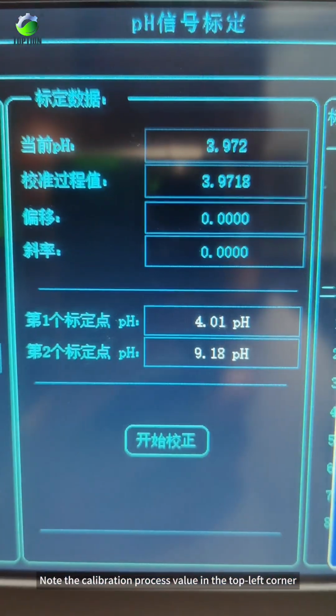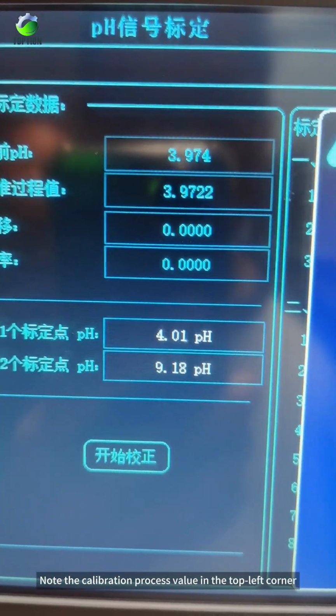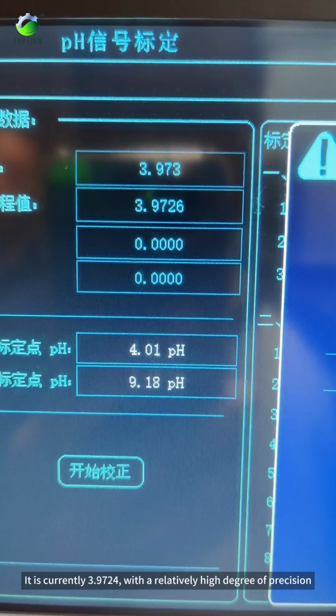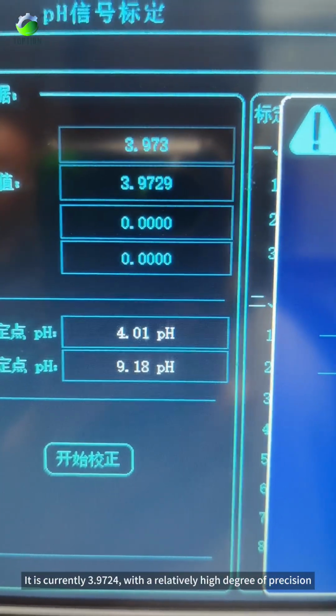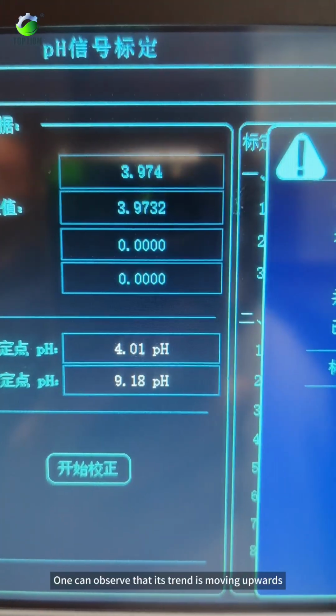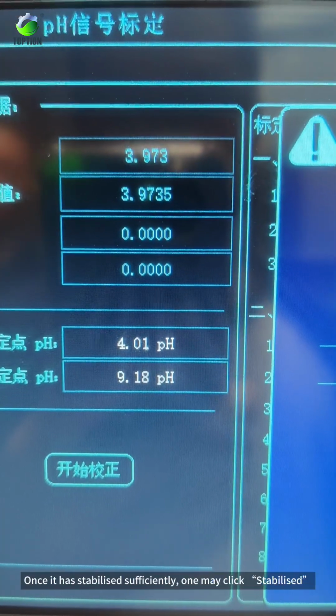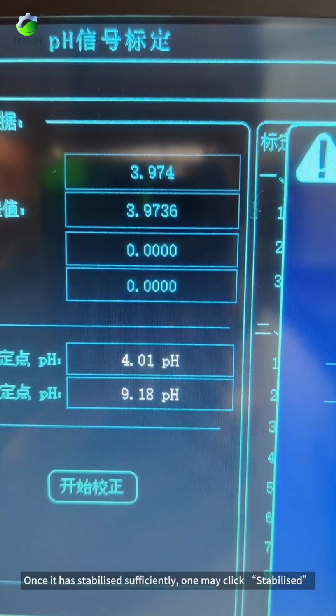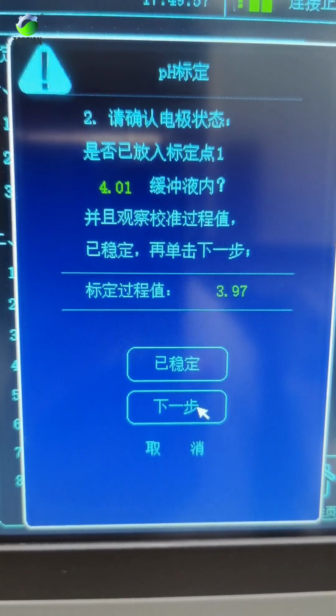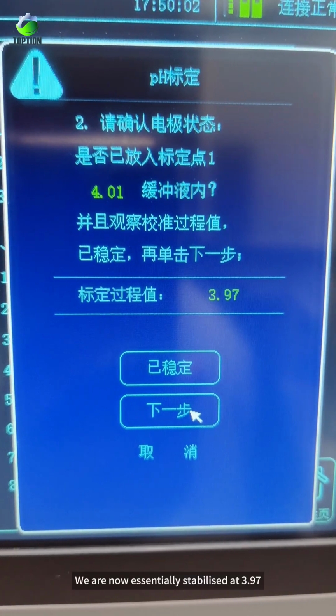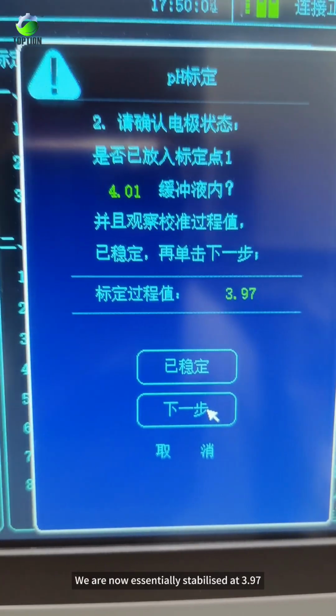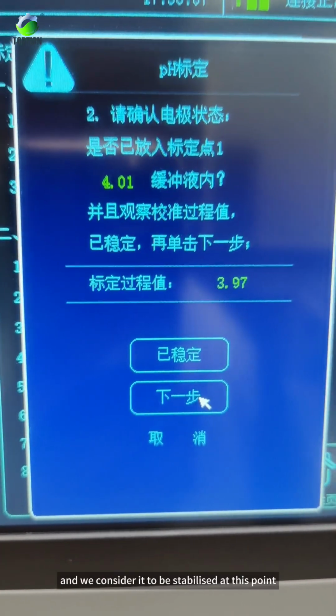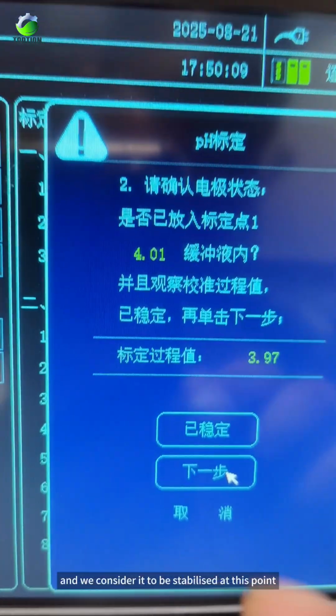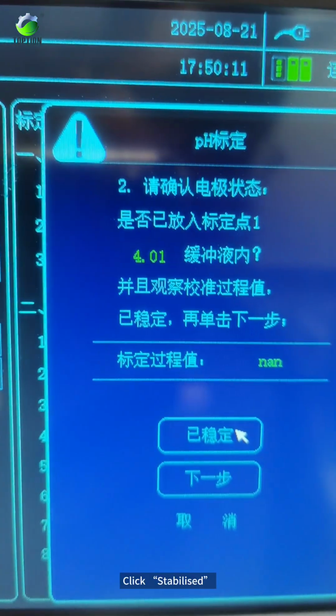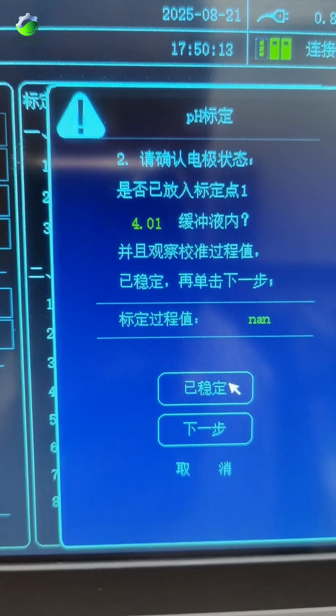Note the calibration process value in the top left corner. It is currently 3.9724 with a relatively high degree of precision. One can observe that its trend is moving upwards. Once it has stabilized sufficiently, one may click Stabilized. We are now essentially stabilized at 3.97, and we consider it to be stabilized at this point. Click Stabilized. Then click Next.